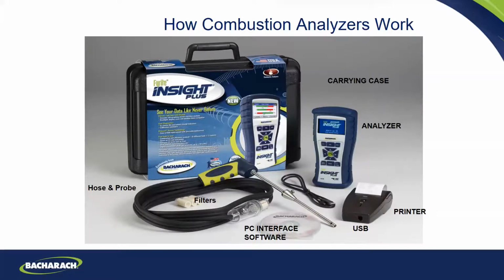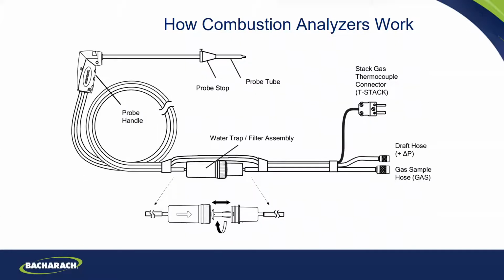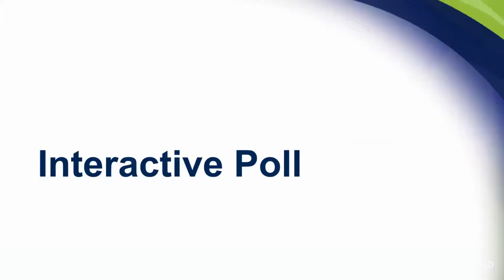If you're in a boiler, it might go up to like 390, 400, 401, down to 398. It's just sort of hovering there. That's where you would take your test. It's steady state efficiency. You're not going to take it as it's ramping up. You do make CO at startup in all these appliances. Okay, so that's how you take it. It's as easy as that to take a combustion test.